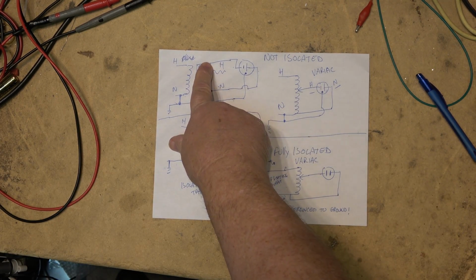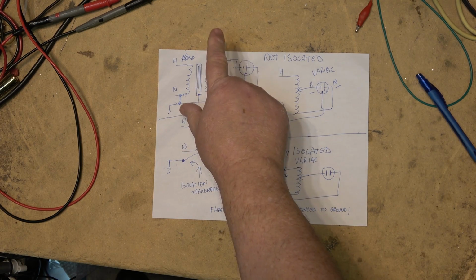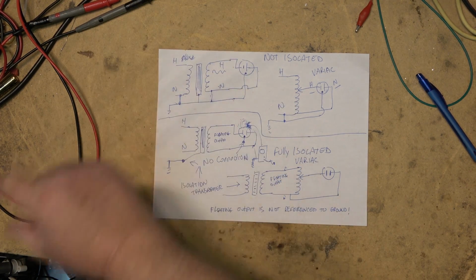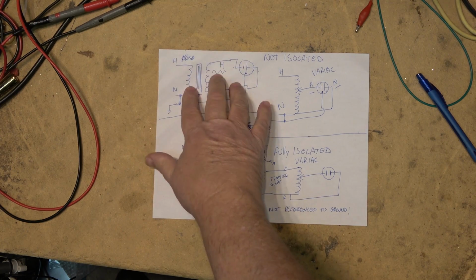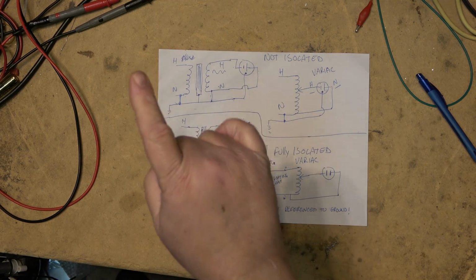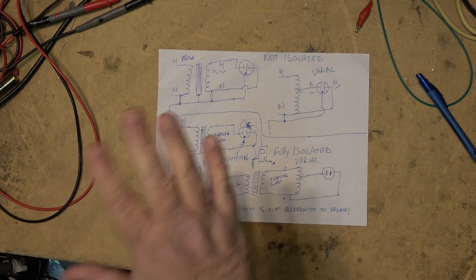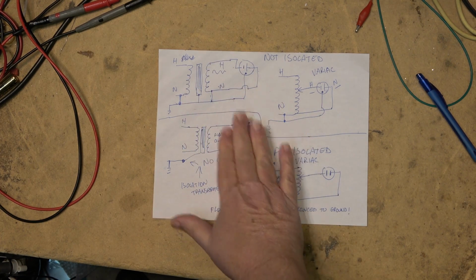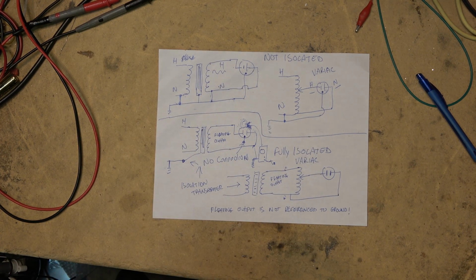This is an isolating transformer, as it isolates the hot side from the utility hot, but it does not isolate the ground. And this is an isolation transformer because it totally isolates the output from the input with no reference to ground.